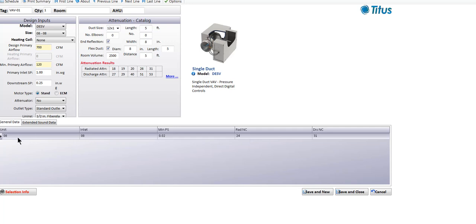My magic rule for sizing inlets is to size the inlet for a maximum inlet velocity as close to 2,000 feet per minute without going over by much. A size 8 box has an inlet area of 0.349 square feet, so 0.349 times 2,000 comes right up to 700 CFM. A size 6 box has an inlet area of 0.196 square feet, so I use a size 6 box right up to 400 CFM. I use a size 10 box right up to 1,100 CFM.